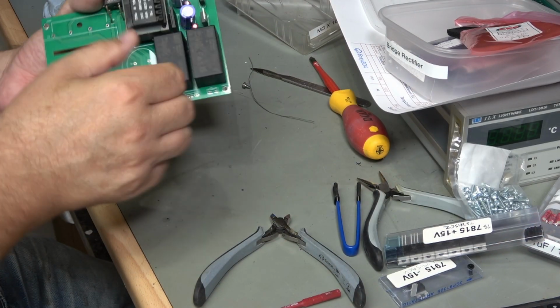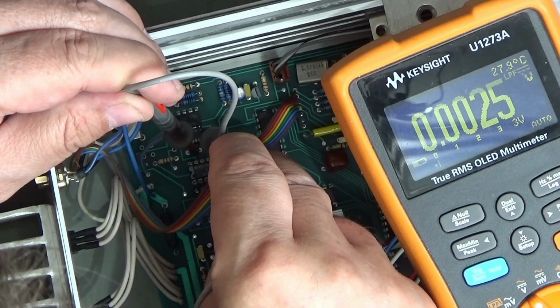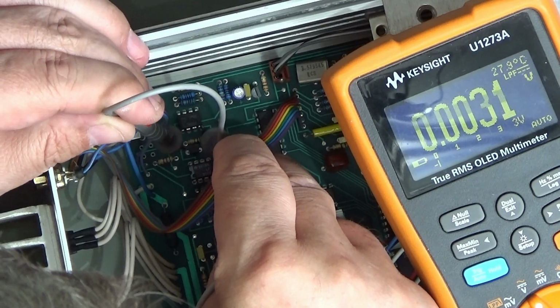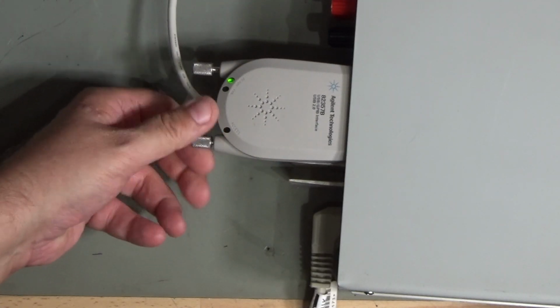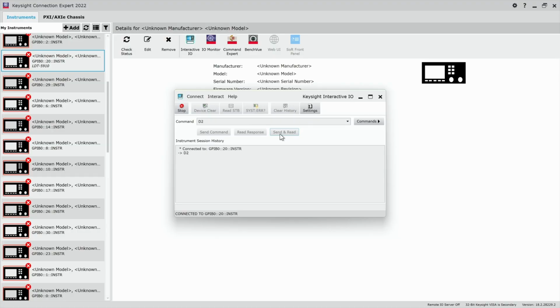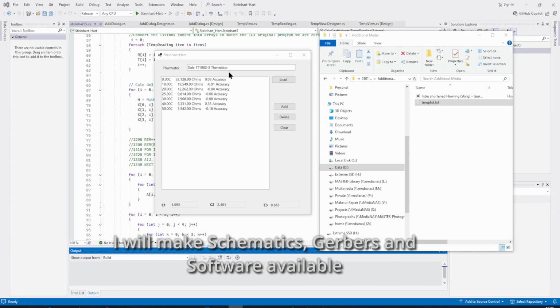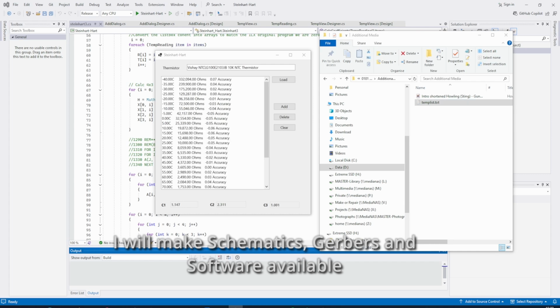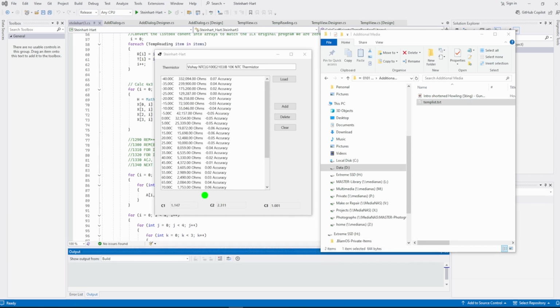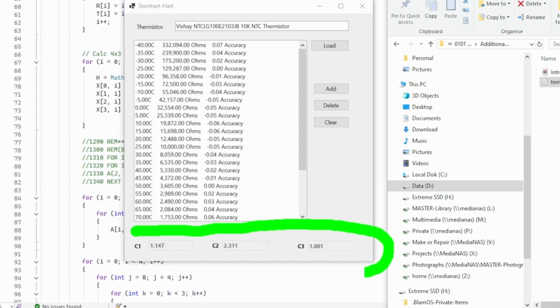So I'll show the power supply replacement fairly briefly, I think, then how I fixed the constant current regulation and resistance sensing. Next I'll calibrate the unit using GPIB commands so that it measures the thermistor accurately. Finally I'll take a quick look at a program that I wrote that obtains the calibration coefficients for a specific thermistor. That helps us crank up the accuracy.